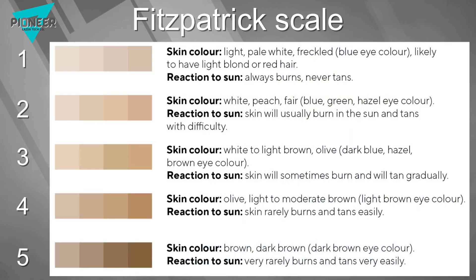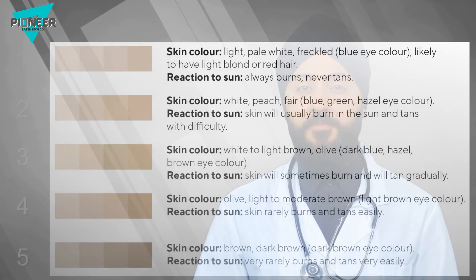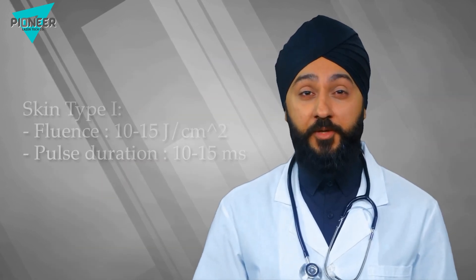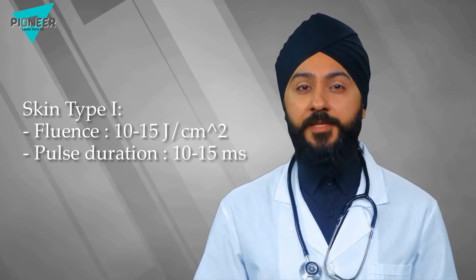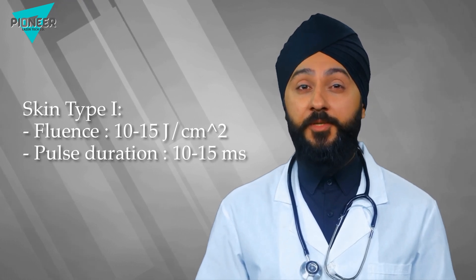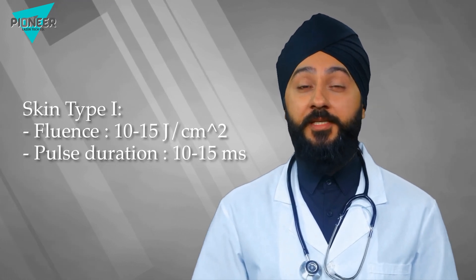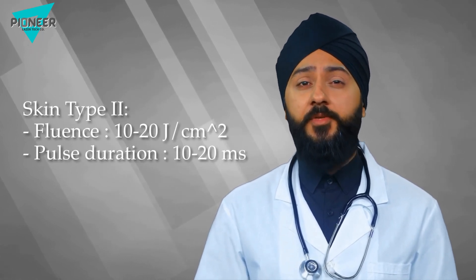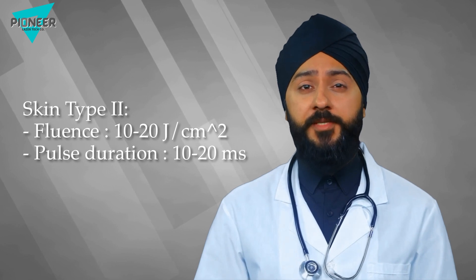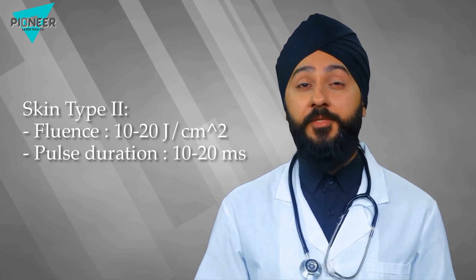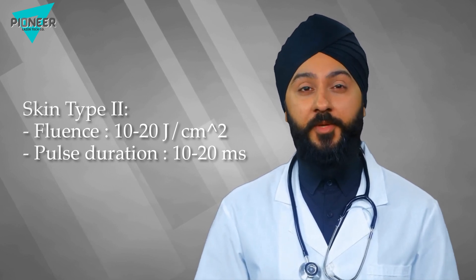Type 1 is the brightest. For skin type 1, we usually set the diode fluence to 10 to 15 joules per centimeter square, with a pulse duration set to 10 to 15 milliseconds. For skin type 2, we set the diode fluence to 10 to 20 joules per centimeter square, with a pulse duration set to 10 to 20 milliseconds, which is slightly higher than what we set for skin type 1.